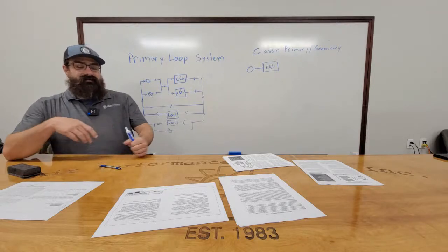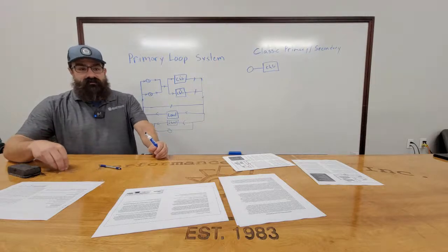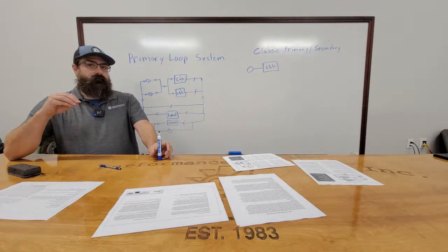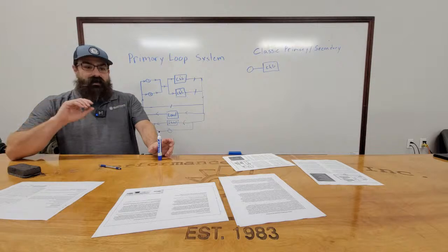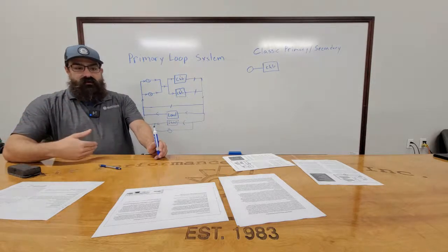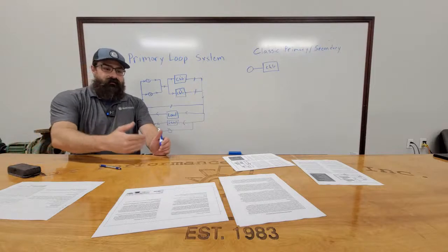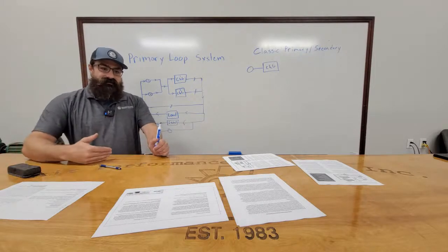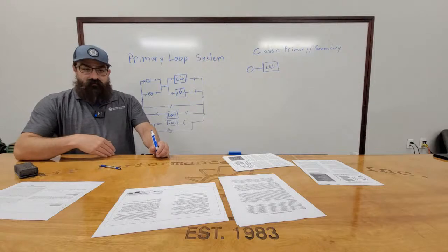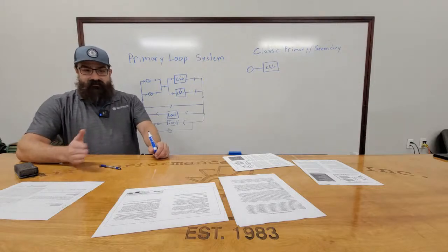So we have isolation valves. The isolation valves are controlled by the chiller. The chiller is network controlled, so we don't have any physical input to the chiller. All I do is pull it in BACnet. I say start or enable or disable. Then the chiller does everything on its own. The only thing it doesn't do is start its own pump. It controls its own ISO valve.